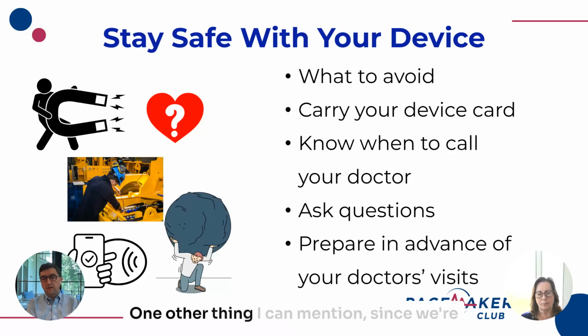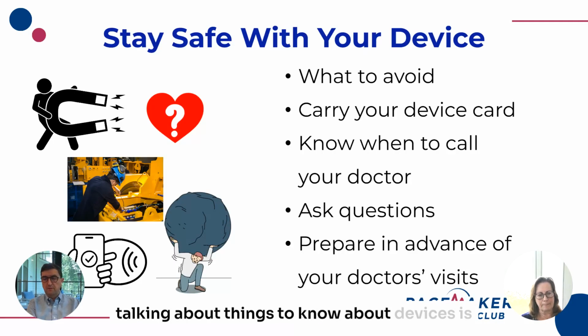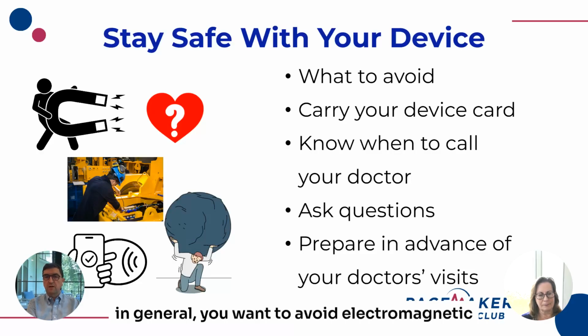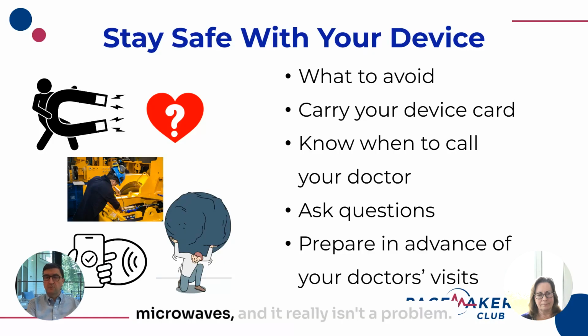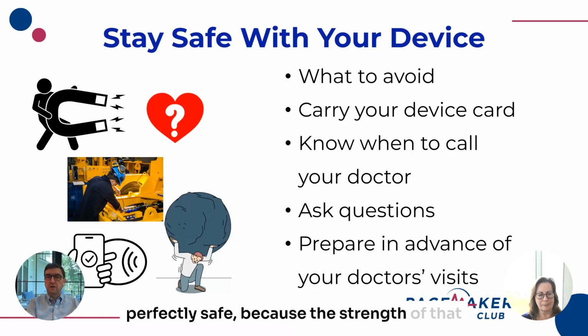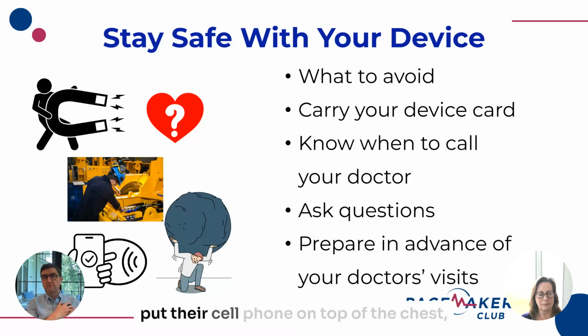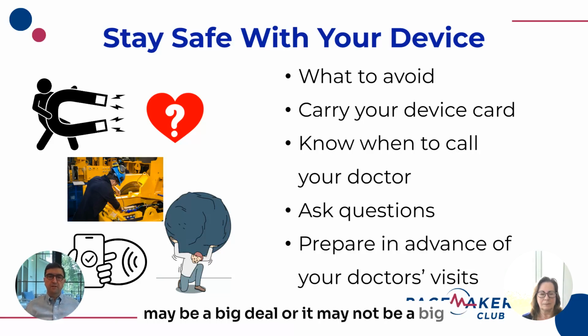I agree with that. One other thing I can mention, since we're talking about things to know about devices, is that in general you want to avoid electromagnetic interference. There are a lot of questions about microwaves, and it really isn't a problem. All the household items are perfectly safe because the strength of that field is low enough. The one exception we usually make is that we ask patients, especially men who have breast pockets, not to put their cell phone on top of the chest, because it's then just a couple of inches or less from the device. Usually what's recommended is keeping it at 6 inches or more from the device. And again, depending on the condition that you have, it may be a big deal or it may not be. If it were really a frequent big deal, we would be talking about it all the time.